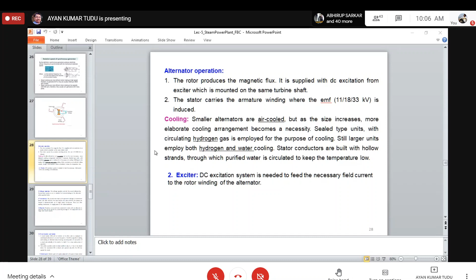The second advantage is that hydrogen has a thermal conductivity around 7 times as great as air. Due to this high thermal conductivity, hydrogen is able to carry away heat across small spaces in the insulation and between laminations more readily than air. Third, on account of the total absence of dirt, moisture, and oxygen, the life of the insulation is increased and maintenance expenses are decreased. One of the most important points is that hydrogen does not support combustion, hence less damage would result in the case of any internal short circuit. That's why we prefer hydrogen cooling over other coolings, specifically over air cooling.